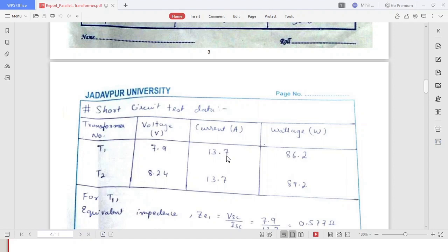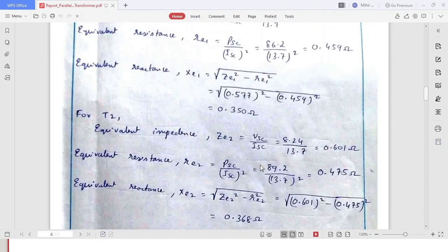Now you can compare the values of the current sharing with the experimental values. Here you see that equivalent impedance will be this one, VSC by ISC, this point 601 ohm for transformer 2. Here RE2 is PSC, this short circuit wattage divided by current square. This will give you the resistance value, and the reactance value you will get from this expression also.